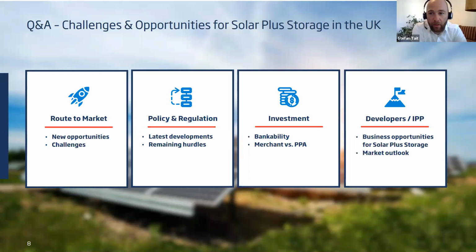Yeah, I can have a quick comment on that. It's a great idea, but I think so far it's probably not cost competitive. The simple cost of a battery for storing, so the cost of one cycle, which then represents the kilowatt hour, and then even the transport to the local customers. My guess is that with today's pricing and costs, that's not a competitive approach, but it might be in a more holistic view in the midterm future, a piece of the puzzle maybe.